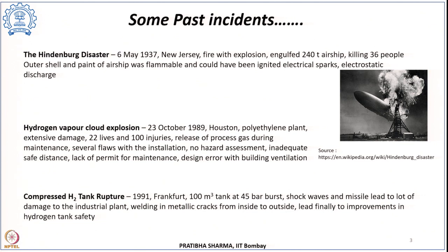Another incident occurred in Houston on 23rd October 1989 — a hydrogen vapor cloud explosion at a very large polyethylene plant, which resulted in extensive damage, took 22 lives, and caused 100 injuries. The release of process gas during maintenance was found to be the reason. On investigation, there were several flaws found: no hazard assessment had been carried out, there was an inadequate safe distance between the control room and the reactor, there was no permit for the maintenance being carried out, and there were design errors with the building ventilation — all of which together led to the catastrophic event.